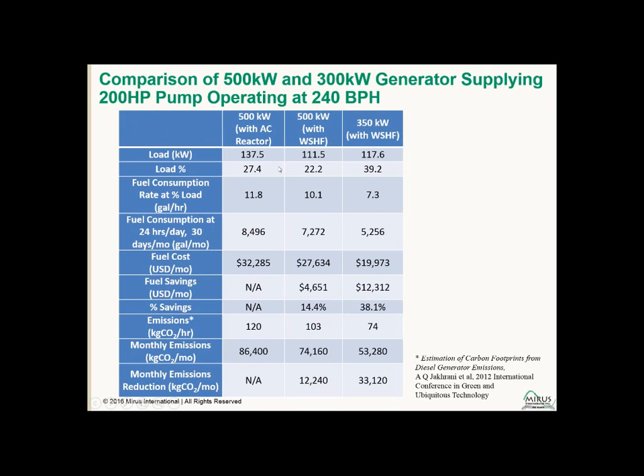So if you look at the percent loading on the generator, there's 27% loading in the first case and 22% loading with the filter. So there's a slightly lower loading percentage, which takes it even further down into the less efficient operating range. But because of the reduction in the kilowatts, there was a substantial reduction in the fuel consumption. So it went from 11.8 down to 10.1 gallons per hour, which operating 24 hours a day, 30 days a month, went from 8,500 to 7,200.